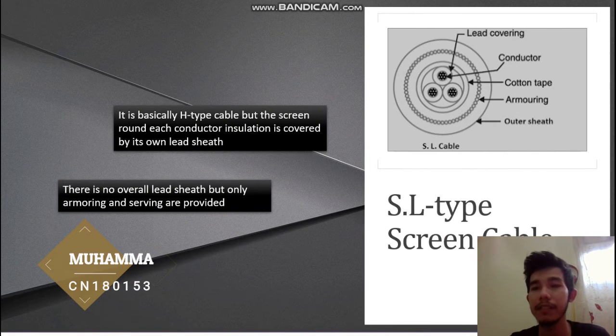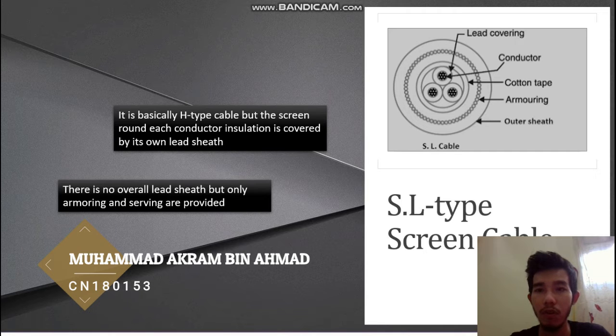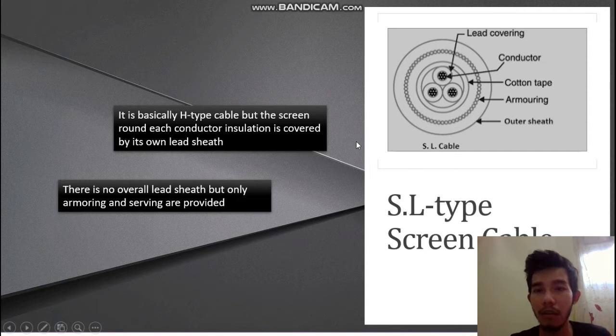Okay, for the next part is the SL-type screen cables. This is the second type of the screen cables. This is the construction of the SL-type screen cable. The center of the SL-type screen cable has three conductors. The first layer is the conductor, and the second layer is lead covering. The lead covering is covering every conductor. So each conductor insulation is covered by its own lead sheath. This is the difference from the H-type screen cables.